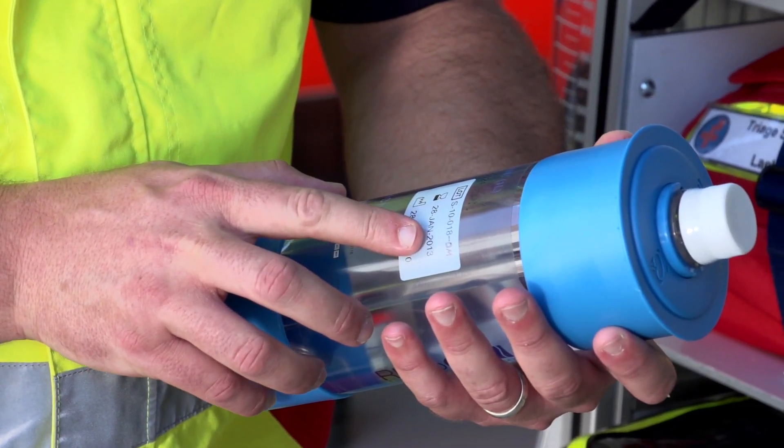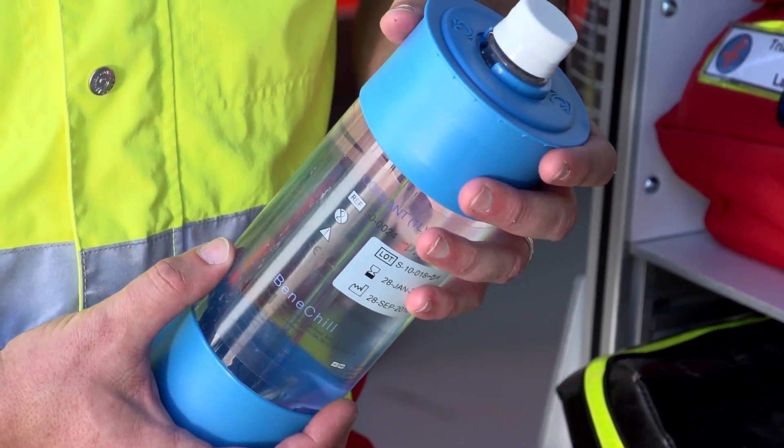The coolant is a completely inert liquid that evaporates easily and forms a fine vapor when pressurized gas is passed through the system. It is supplied in one-liter, single-use bottles that last approximately 30 minutes at the medium flow rate setting.